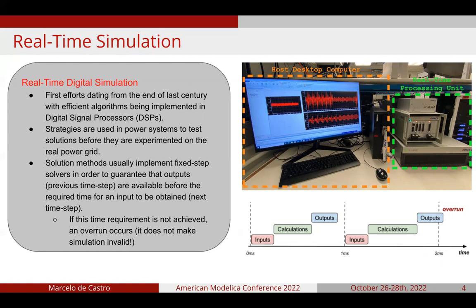This type of simulation is incredibly important in the study of power systems because it enables us to test solutions before they are actually implemented in the real world, in the real power system. Nowadays, real-time solutions usually implement fixed step solvers in order to guarantee that the reading of inputs, the execution of calculations, and the releasing of outputs is done within a time step interval. When this is not possible, we say that an overrun has occurred, and this does not mean that the simulation is invalid, but that that particular time step was not real-time compliant.